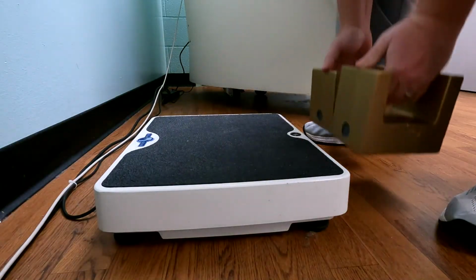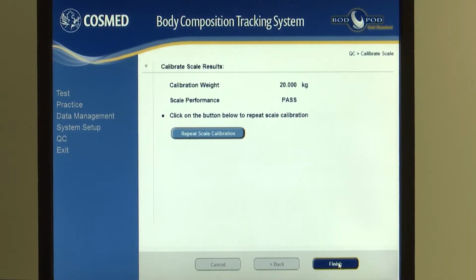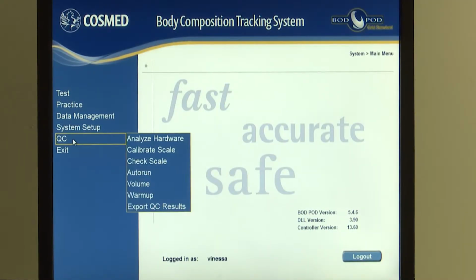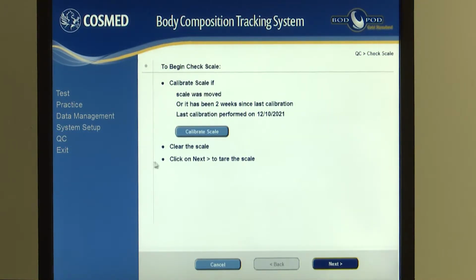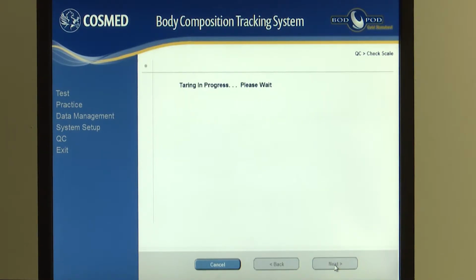The screen will indicate if the calibration was a pass or fail. If the test fails, it must be repeated. If it passes, go to the next step. Go back to the QC tab, open the drop-down menu, and click Check Scale. The screen will state when the calibration was last completed. This calibration must be done every 2 weeks. If it has been longer than 2 weeks, click the Calibrate Scale tab to do the test that was just completed. If it is within 2 weeks, click Next.